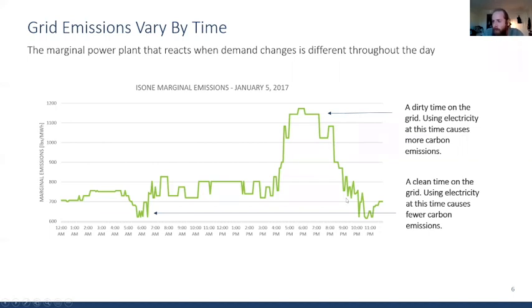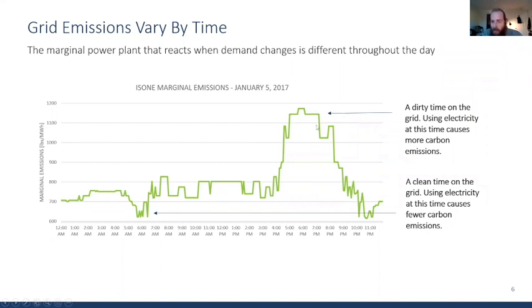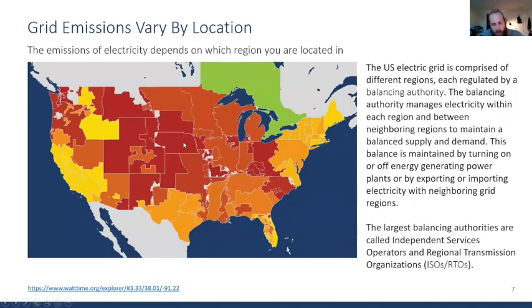On timing: you want to avoid demand peaks and move as much electricity into the troughs as possible. Efficiency measures that address the peak are more valuable than those at off-peak periods. We also talk about automated load shifting — if you have an EV, a smart thermostat, or a connected appliance, can it run in the morning trough or when there's wind curtailment instead of the afternoon? From a location standpoint, if you're a large corporation siting a data center, don't place it where added load increases demand for coal generators; place it where it increases demand on hydro in Quebec or solar in California.